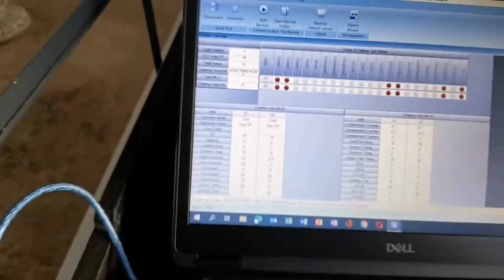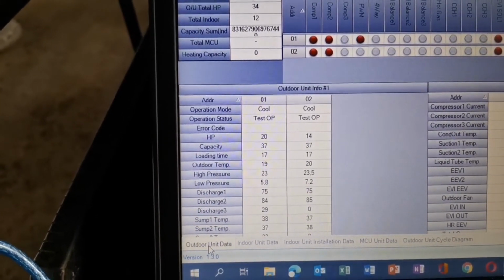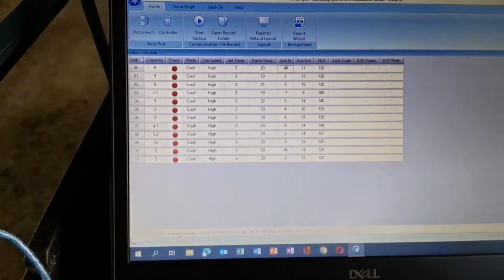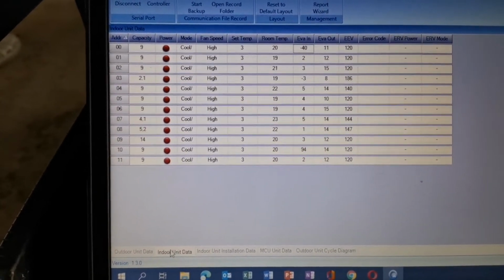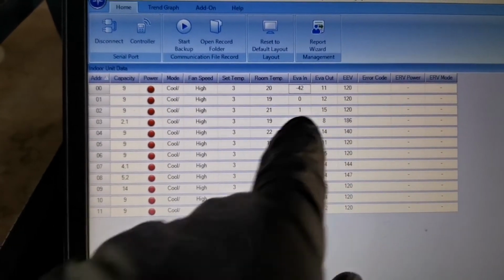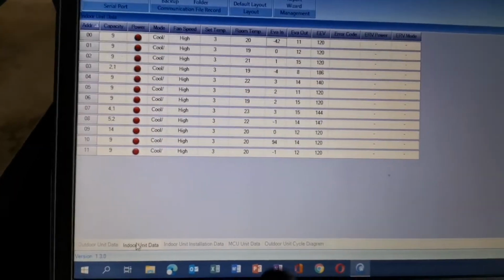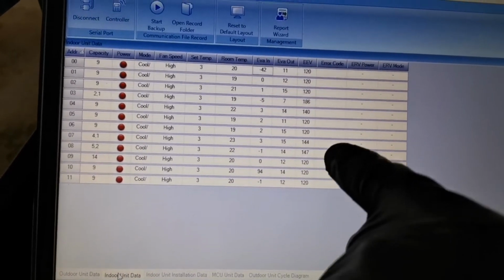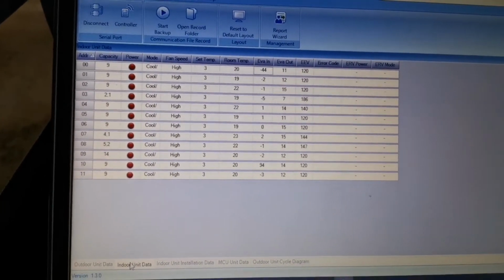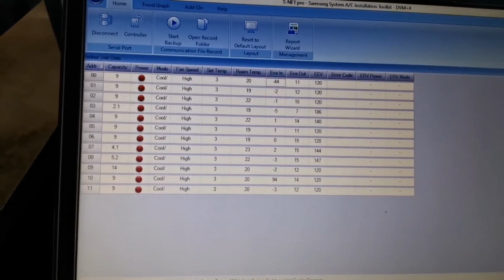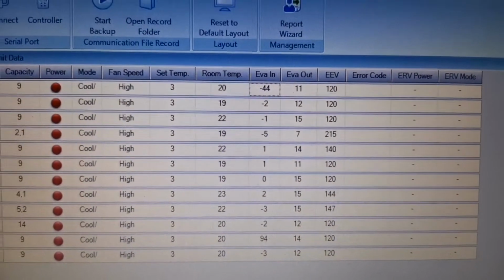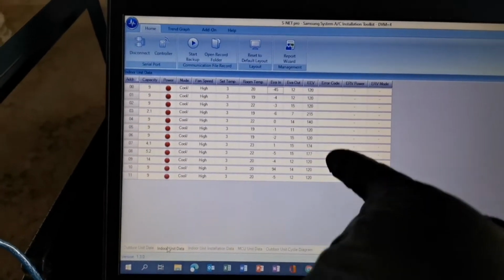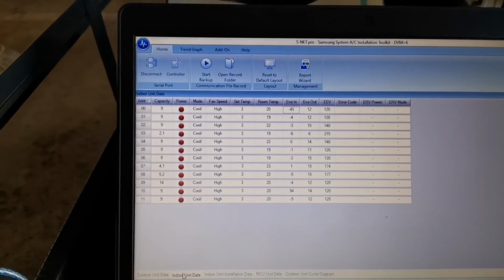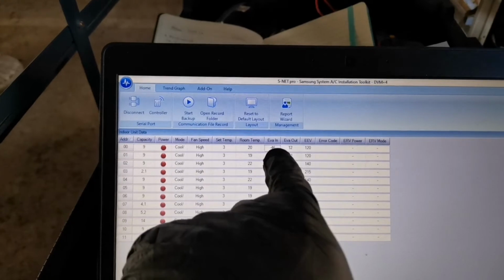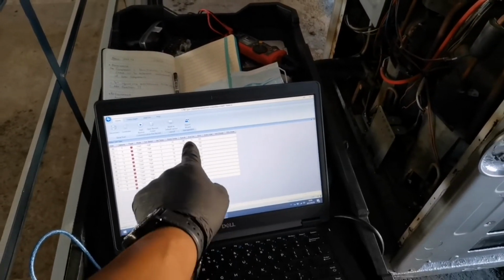Alright, so test operation. Let me give you guys a closer look. We're in test operation now, so if we have a look at our indoor unit data, see those temperatures? Most of them are out of the negatives. There's one more that's at -3, but that's minor. I'm not worried about gas pressures, because if you have a look at my EEVs right here, they're very happy. We're only at about 120, the highest is 215 steps, and these typically go all the way to 1,500 steps. That's maximum. So we definitely have a sensor that needs to be replaced, and the one right on top. Fantastic. So we more than likely will have to get that indoor model number and get those sensors changed out.